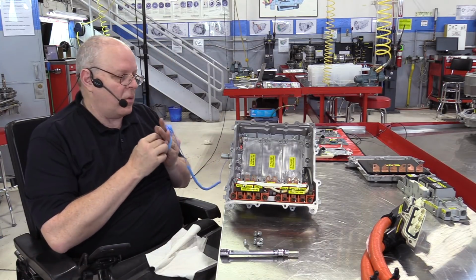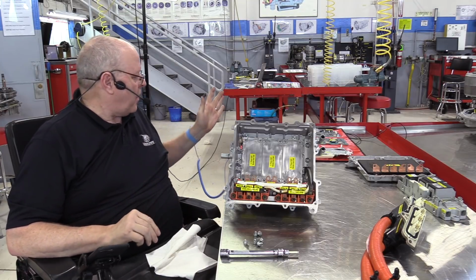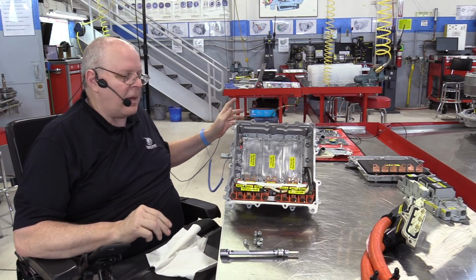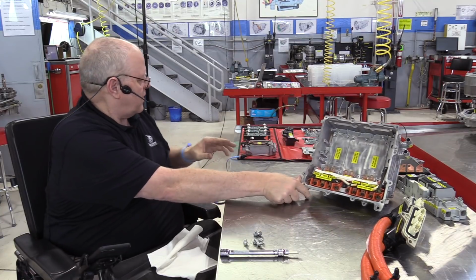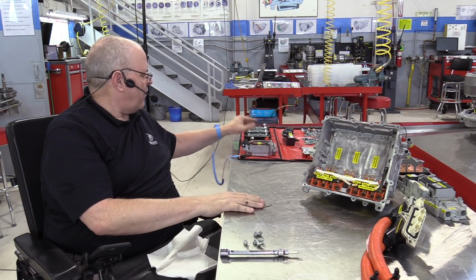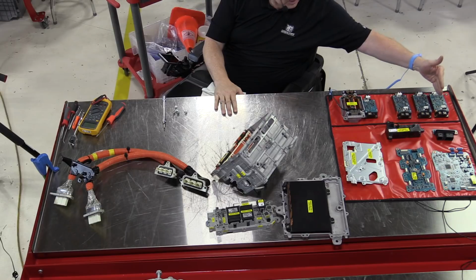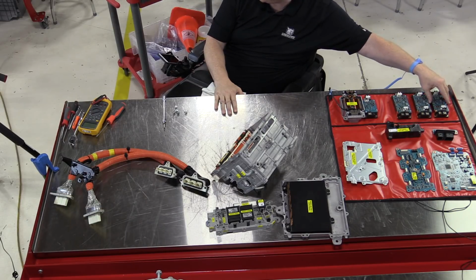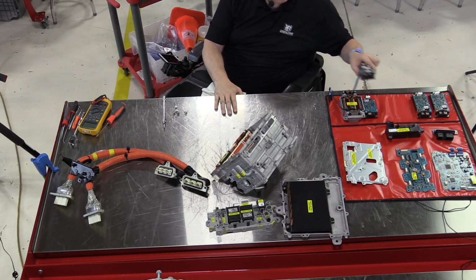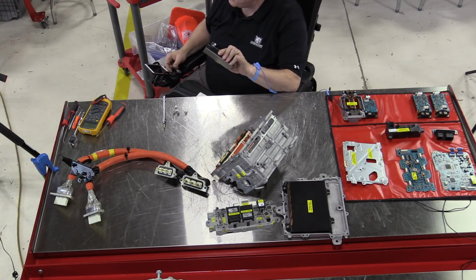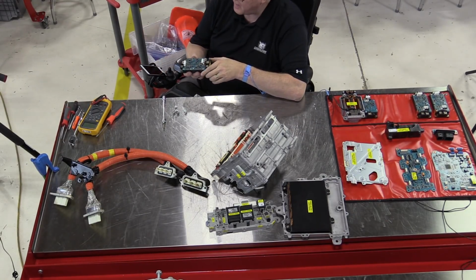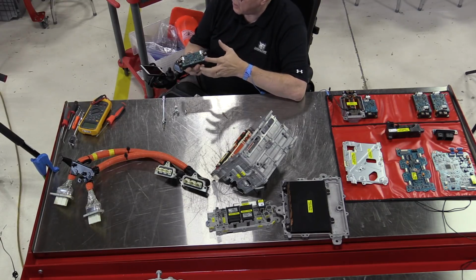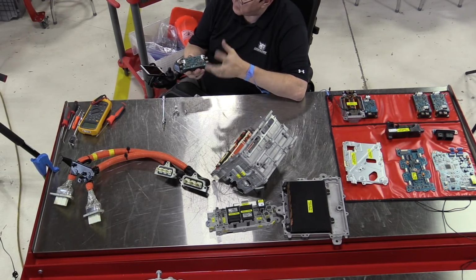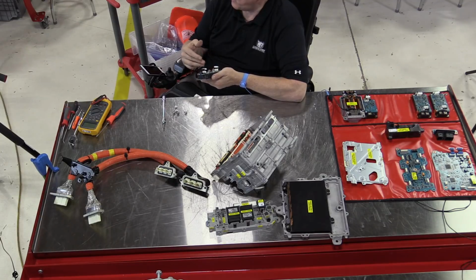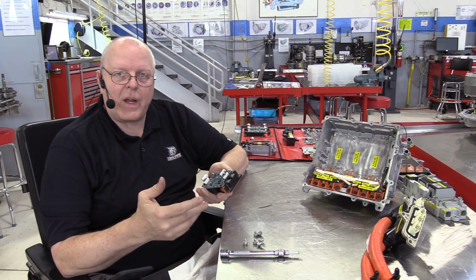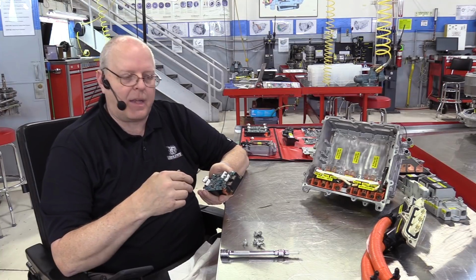Okay, so our connectors are connected, and we've got our bus bar connected. The next thing we want to connect up are the IGBT modules, and these modules I've got laid out over here. We've got 3 IGBT modules that have 4 IGBTs per module. An IGBT is a power transistor. It can turn on and off very quickly, can handle a whole bunch of current, and it also has a diode across it. And the diode is used for when we decelerate. It's used for rectifying the AC voltage and turning it back into DC.